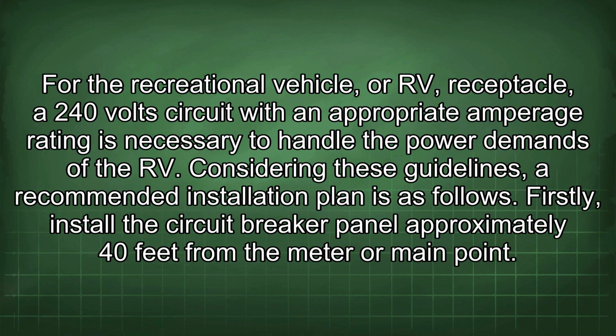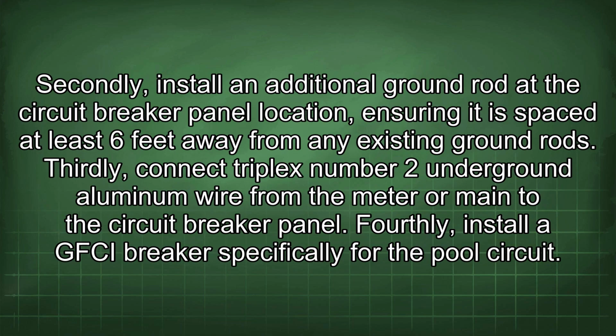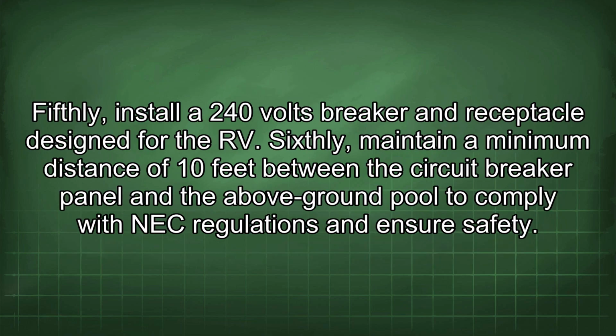Firstly, install the circuit breaker panel approximately 40 feet from the meter or main point. Secondly, install an additional ground rod at the circuit breaker panel location, ensuring it is spaced at least 6 feet away from any existing ground rods. Thirdly, connect triplex number 2 underground aluminum wire from the meter or main to the circuit breaker panel. Fourthly, install a GFCI breaker specifically for the pool circuit. Fifthly, install a 240 volts breaker and receptacle designed for the RV. Sixthly, maintain a minimum distance of 10 feet between the circuit breaker panel and the above-ground pool to comply with NEC regulations and ensure safety.